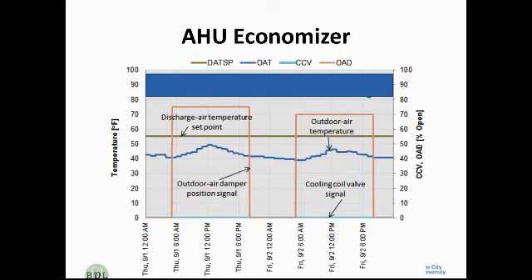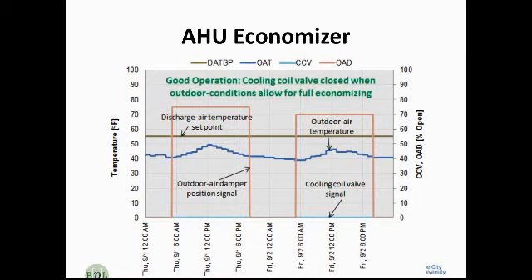Another example, similar situation. Once again, we've got our dampers open during the day, the outdoor air dampers. They're open 75% on the first day and 70% on the second day. The discharge air temperature set point is once again at 55 degrees. Outdoor air temperature varies from 40 to 50. Good opportunity for economizing all day long, and that's what we're doing. We've got those dampers open.